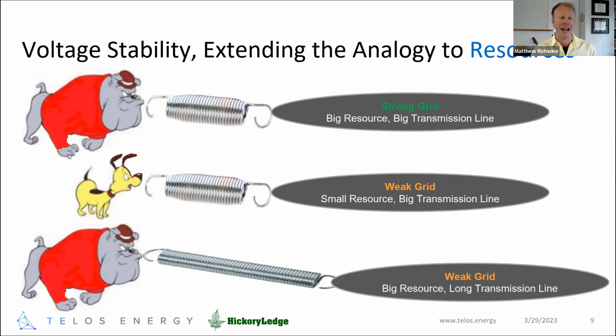The result would be that in that region you'd expect a strong grid because you have a big resource and a short transmission line. In contrast, you could have a small resource there. So Chester, not quite as big and robust as Spike, is tied to the grid via a relatively short transmission line, but that area can have a weak grid because of that small resource, despite the substantial transmission. Blending the two together, you can also get a weak grid if you have a big sturdy resource separated by a long transmission line, or if the point in the grid you're looking at is far from that resource.